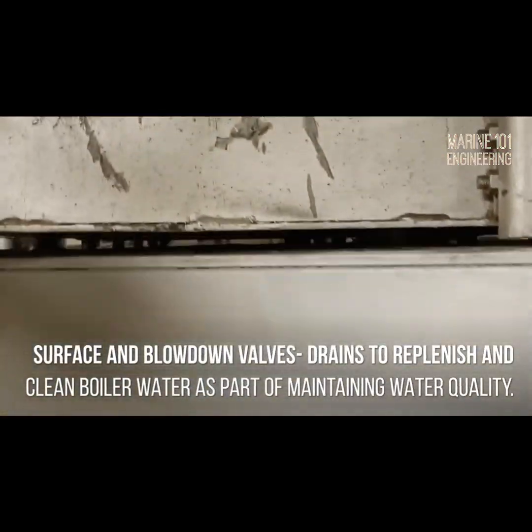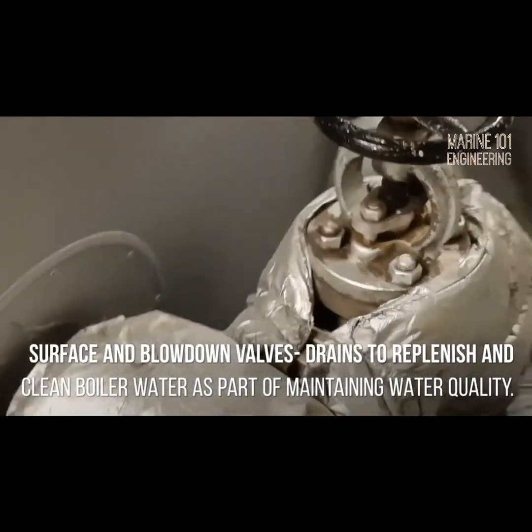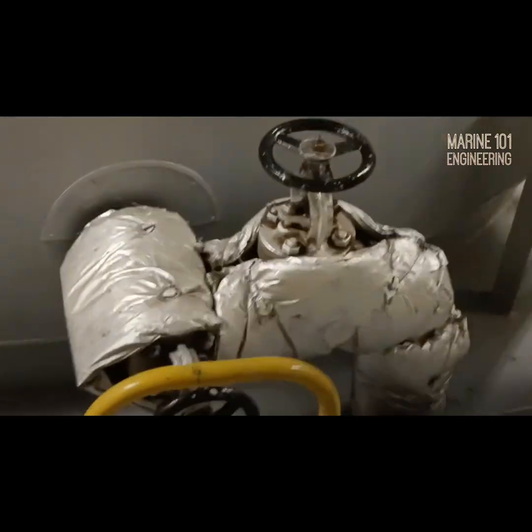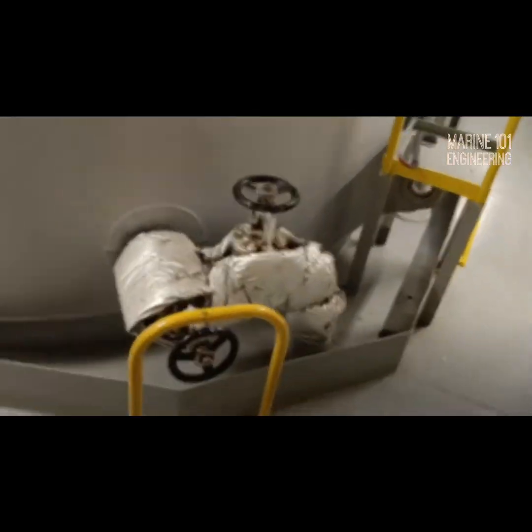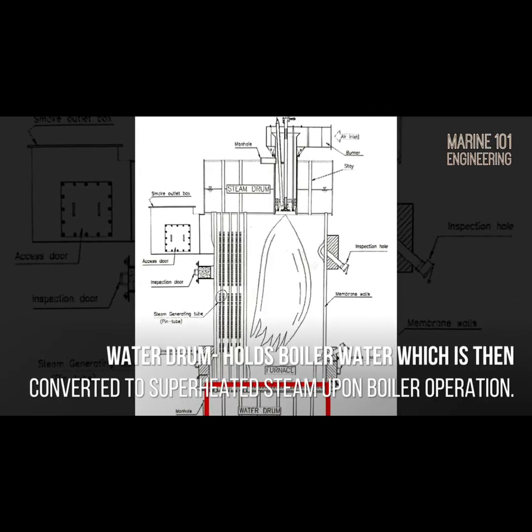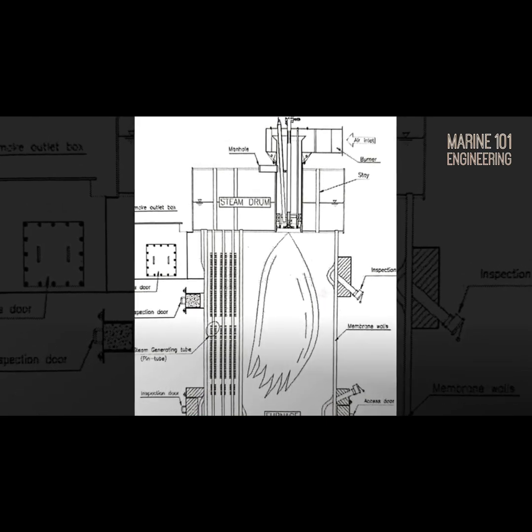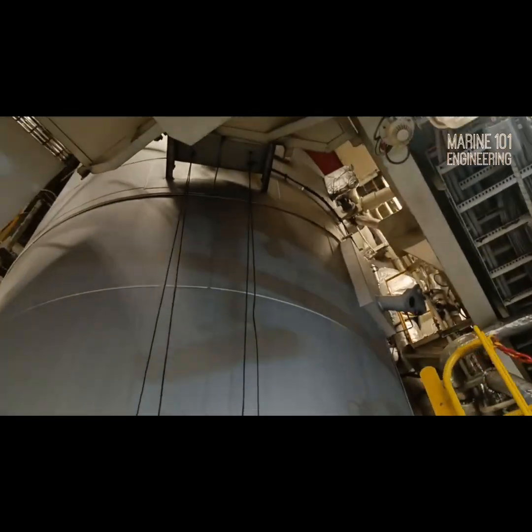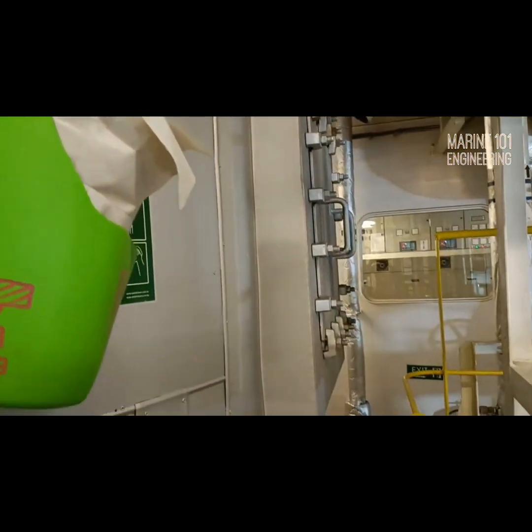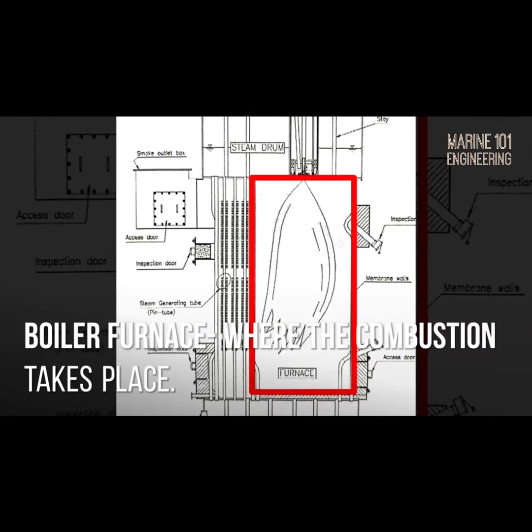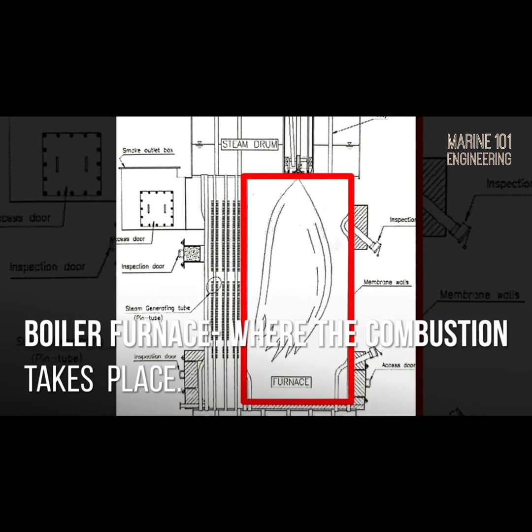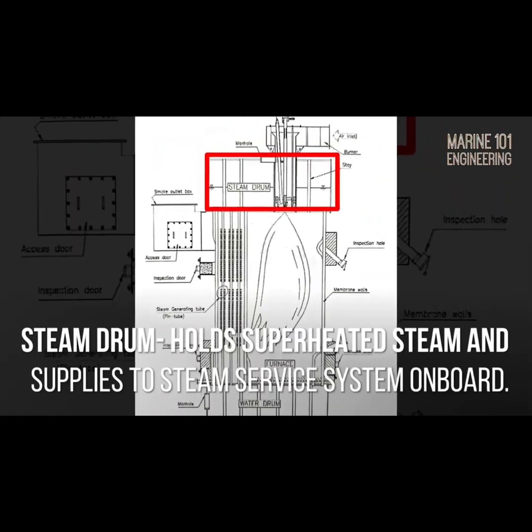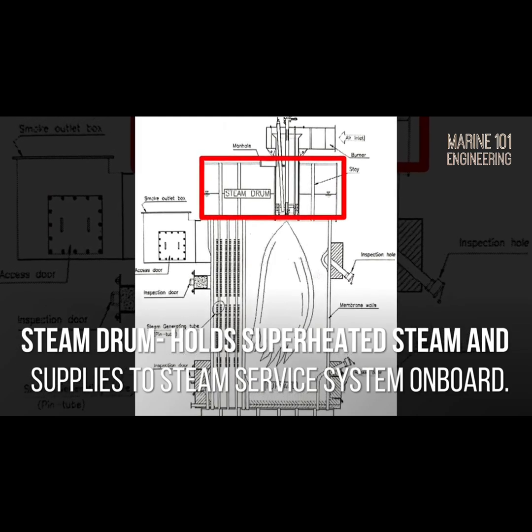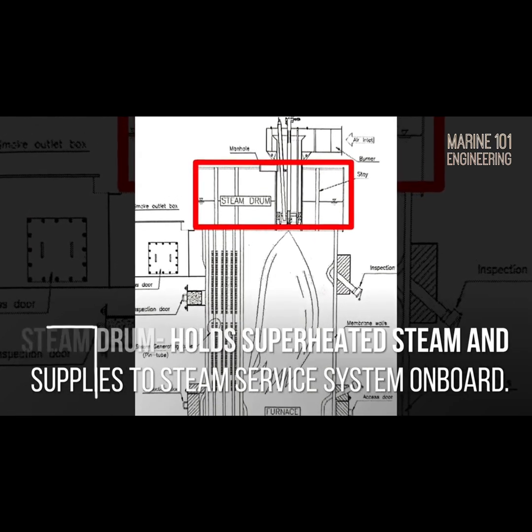Surface and bottom blow down valves are used for draining water from the water tubes, typically to control water quality based on onboard water test results. Water drum holds the water being used for steam production. The boiler furnace serves as the combustion chamber for firing and heating up of water. Steam drum holds the generated superheated steam from boiler operation.